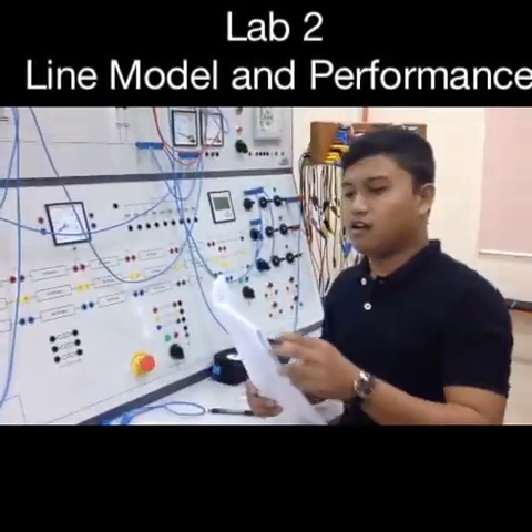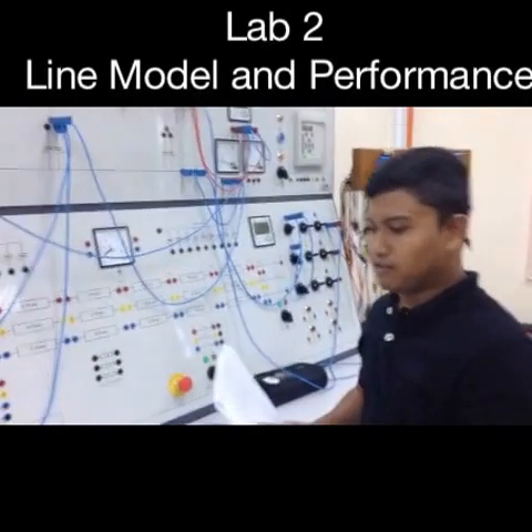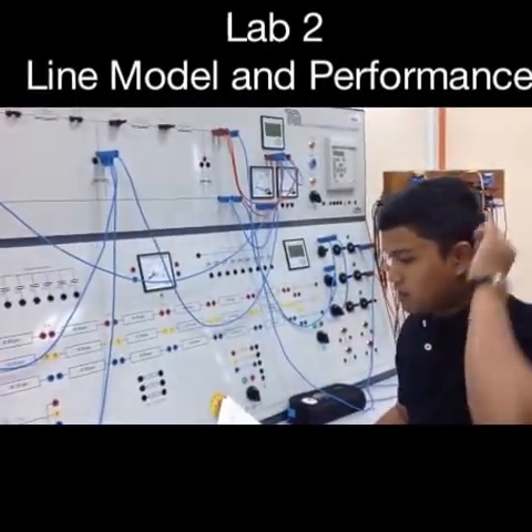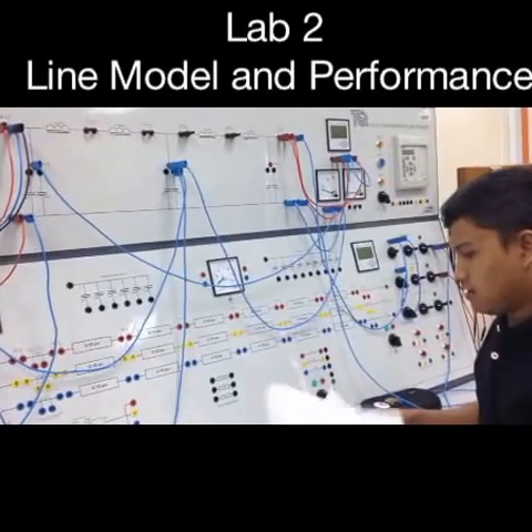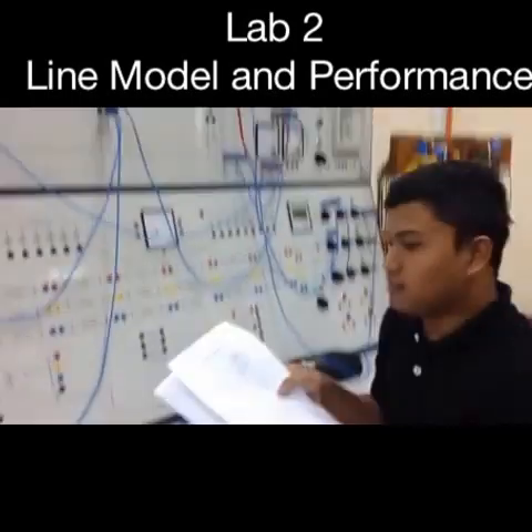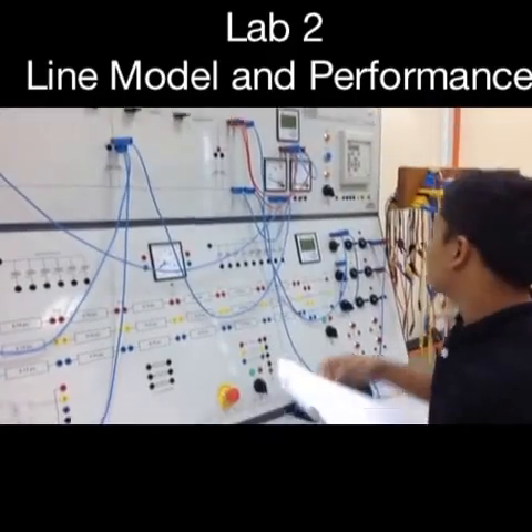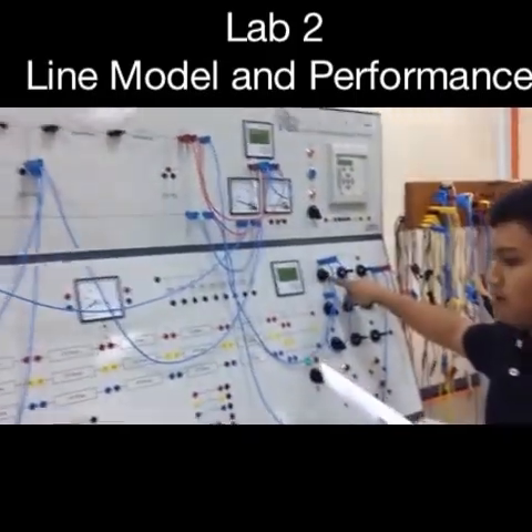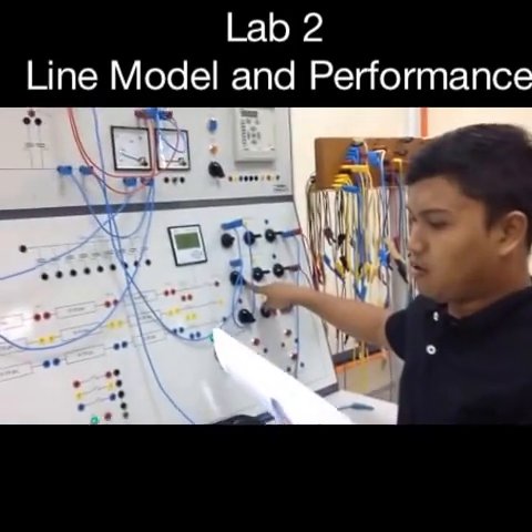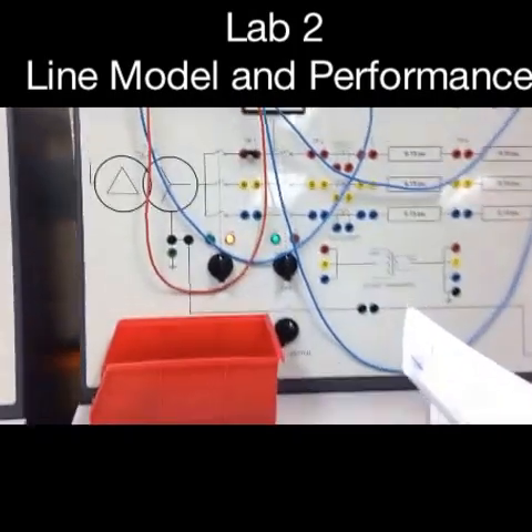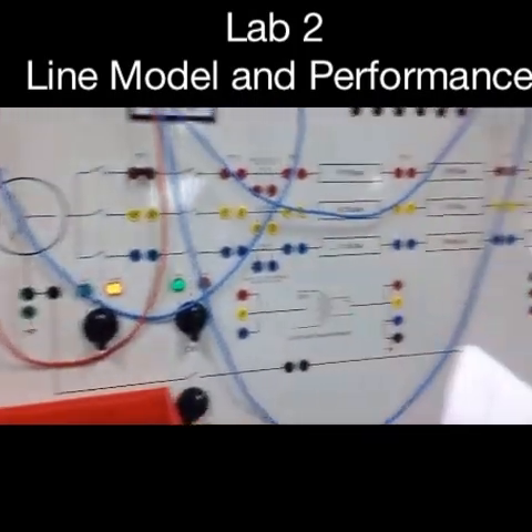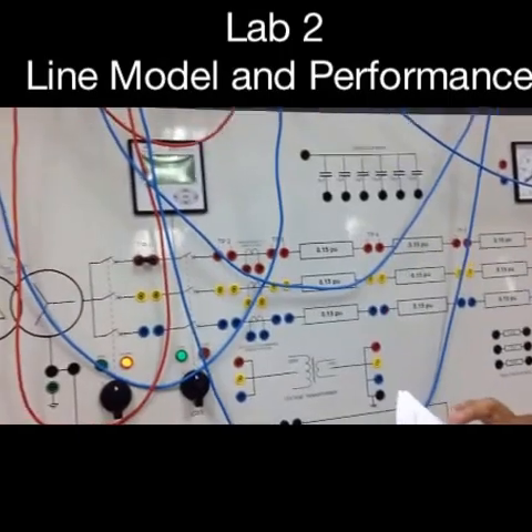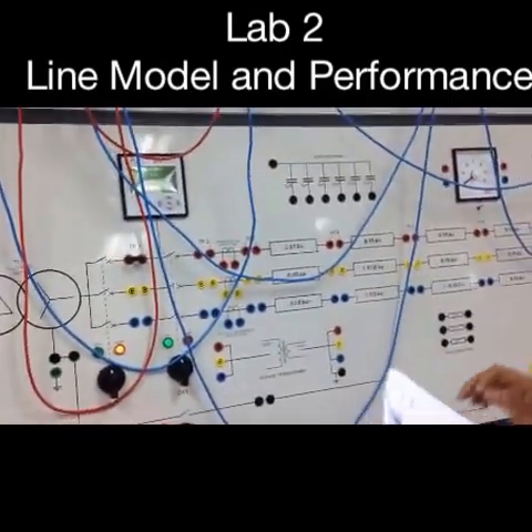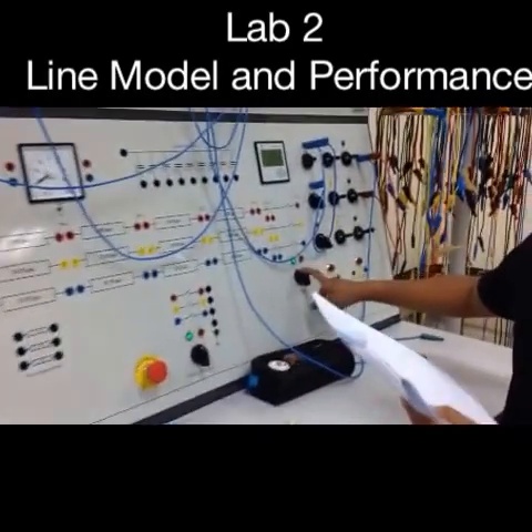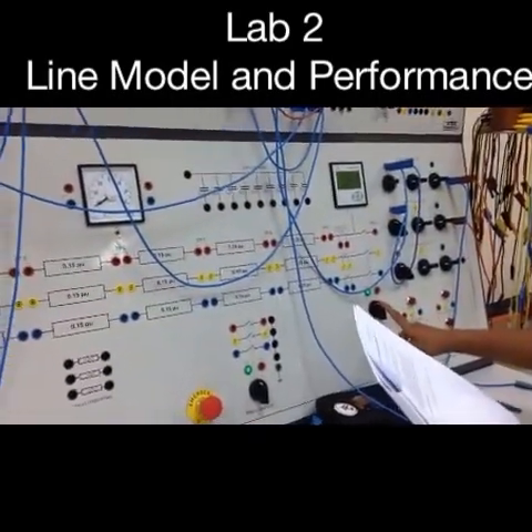Thank you. I'm going to present experiment 3. First, connect the circuit as shown in appendix C. Connect this. Select a 100% resistive and 50% inductive load. Then second, shut CB1 at the secondary of the supply transformers and CB2 at the same end of the single phase line. Disconnect power to the line. Close CB4 to connect the multifunction meter in the lower panel correctly and complete the line.